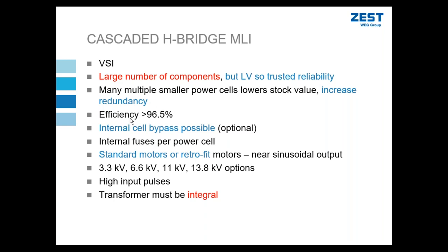The efficiency is not as high as the NPC. Yeah, we're talking about 96.5% compared to the previous 98.5 to 99%. This is for two reasons. Because we're adding more IGBTs, there's more switching, but also because here we have to have an integral transformer. It does not make sense for us to put an oil type transformer outdoors. So it means that the heat losses from the transformer have to be taken into consideration. As I've mentioned, we do have internal cell bypass possible. If you lose one cell, it can be bypassed, and you can continue to operate at reduced output capacity.